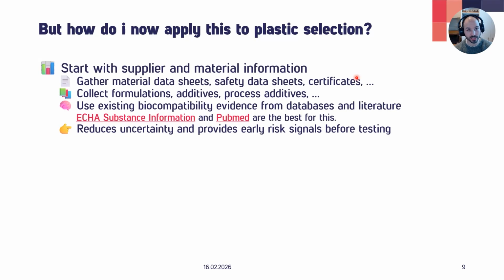So number one is during the material selection phase, we should start with gathering supplier data as much as possible. So data sheets, safety data sheets, certifications. If you're able to, get a formulation, understand what additives are used, what processing aids are used. Sometimes you'll even get biocompatibility testing reports from your suppliers. And you should use this existing evidence to inform your biological risk assessment.